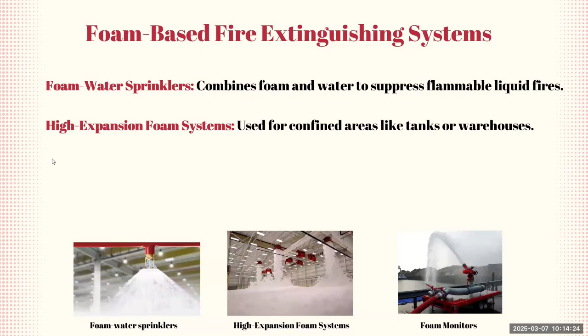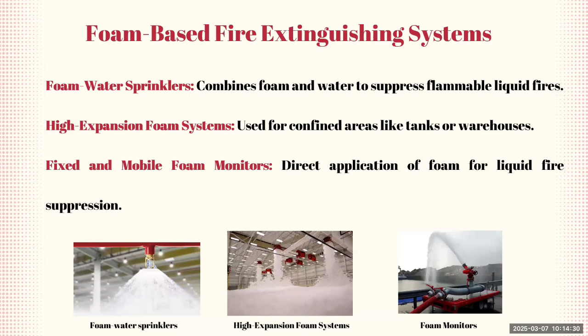We have foam water sprinklers, which are like water sprinklers but combine foam and water to suppress flammable liquid fires. Then we have high expansion foam systems, which can be used for confined areas like tanks or warehouses, as you can see in the image. Lastly, like the water monitors, we also have foam monitors, which can directly apply foam for liquid fire suppression.